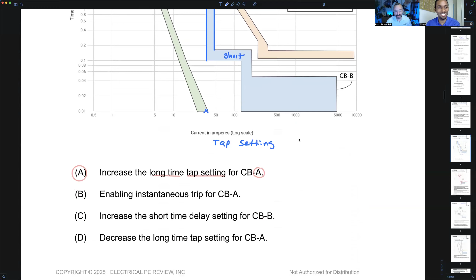So a few of the other answer choices: enabling instantaneous trip for circuit breaker A. Currently circuit breaker A in beige doesn't have the instantaneous trip turned on, you can tell because there's nothing here. Instantaneous trip is usually from 0 seconds to 0.05, exactly where the blue region is. What would happen if we turned on the instantaneous trip, maybe about here for circuit breaker A? Would that help or make even worse miscoordination? Even worse, yeah, so that can't be it.